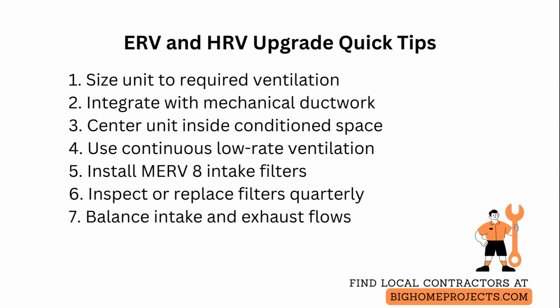Balance intake and exhaust flows at final commissioning with a simple vane anemometer or by using the unit manufacturer checklists so that you achieve near neutral pressure within the house. If you suspect persistent imbalance, tune dampers and verify external wind and stack effects are not driving uncontrolled flows.